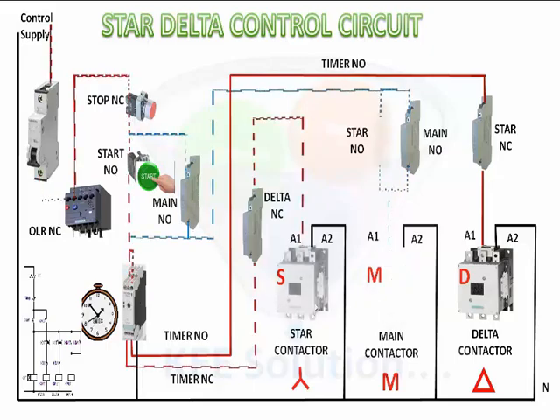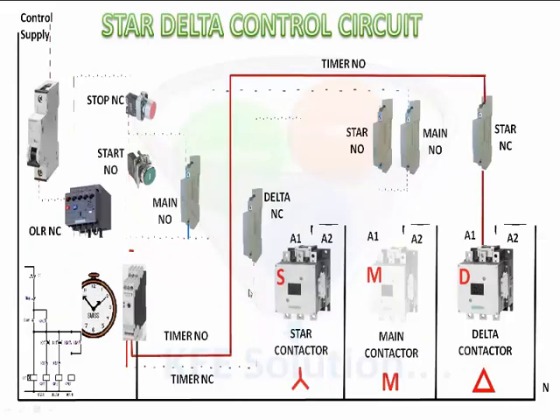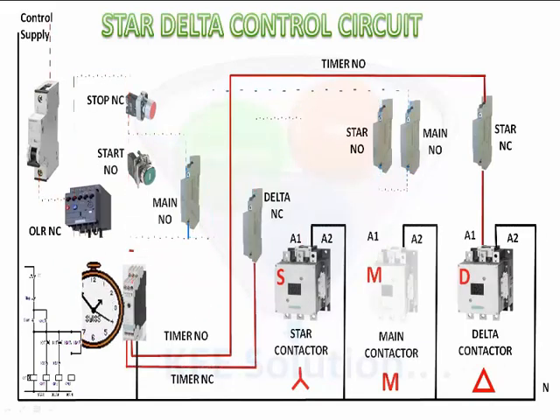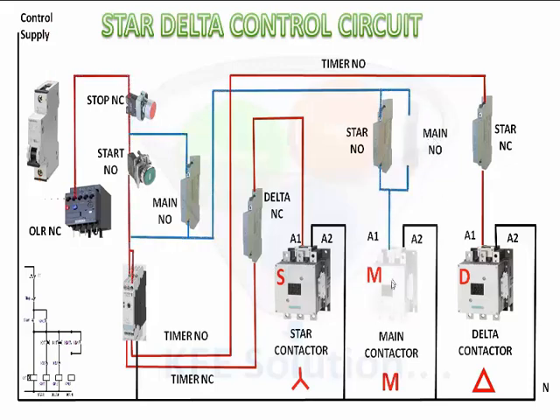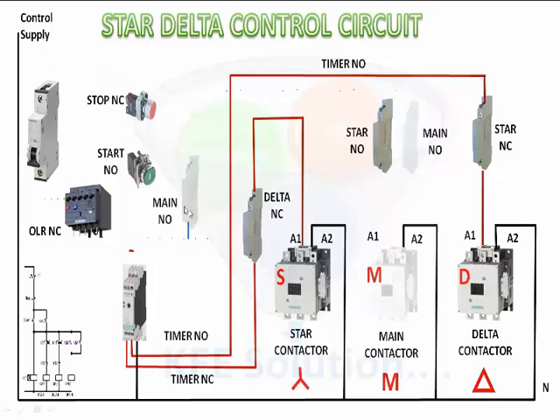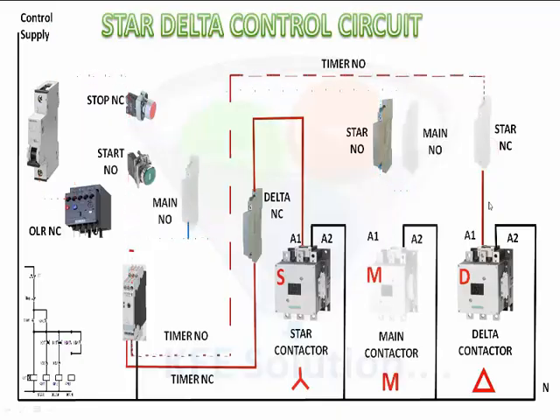Now the motor will run at star connection initially and the timer runs. When the timer completes its time, the star contactor will stop and timer NO will give power to the circuit. When the main contactor is on, the power will go through main NO and hold, and timer NO will give power to the star NC contact, which will actuate the delta contactor.